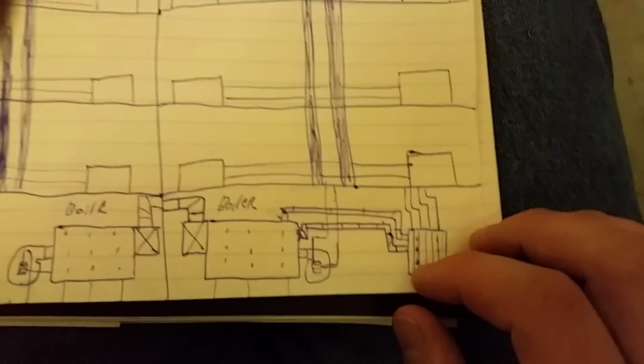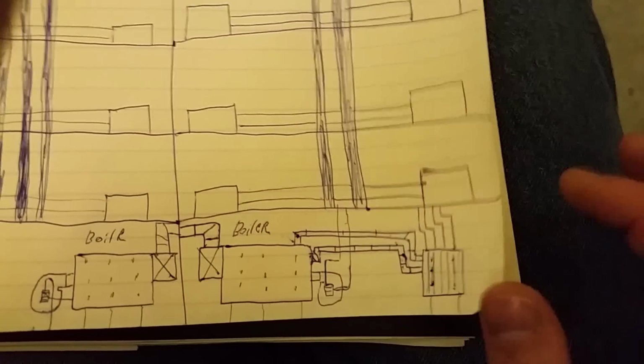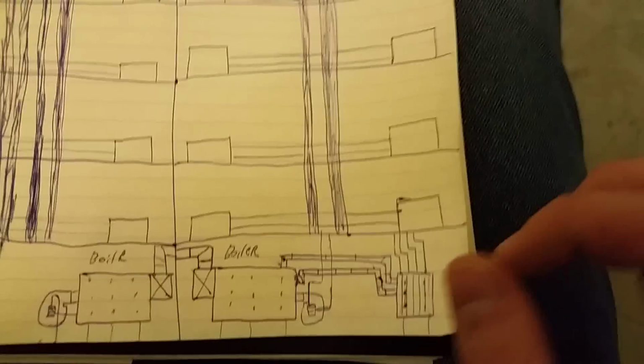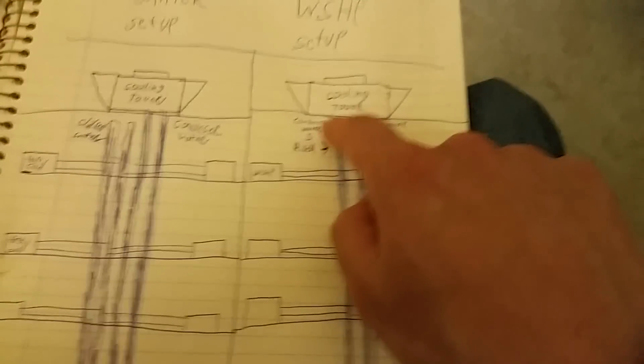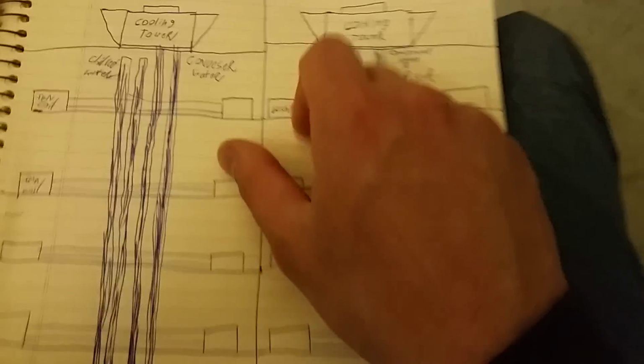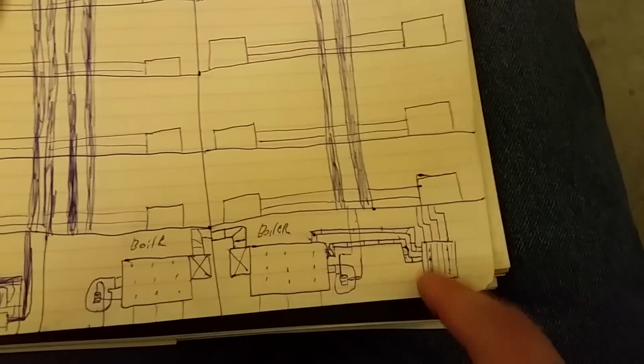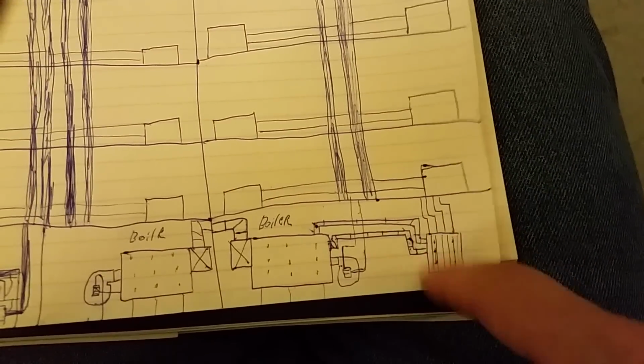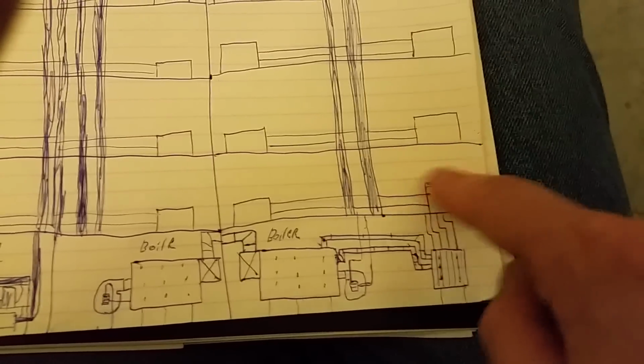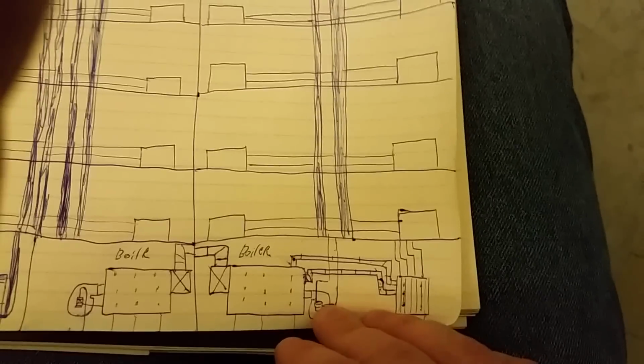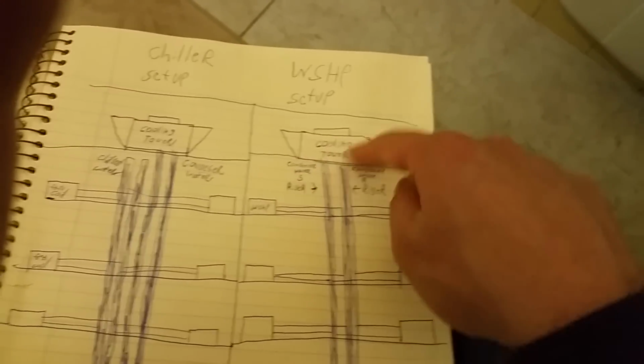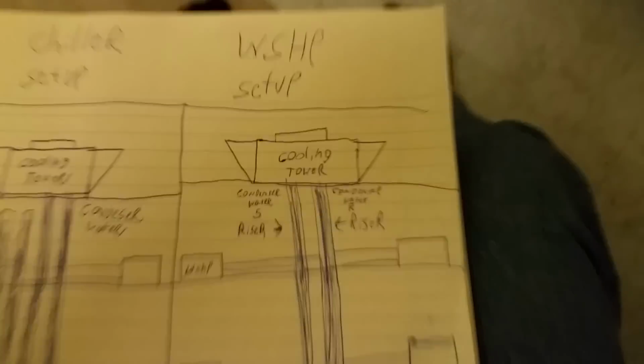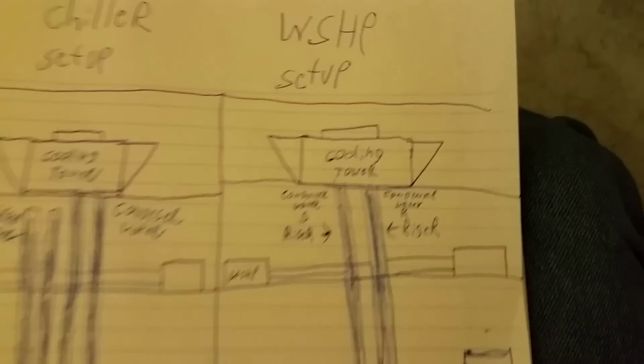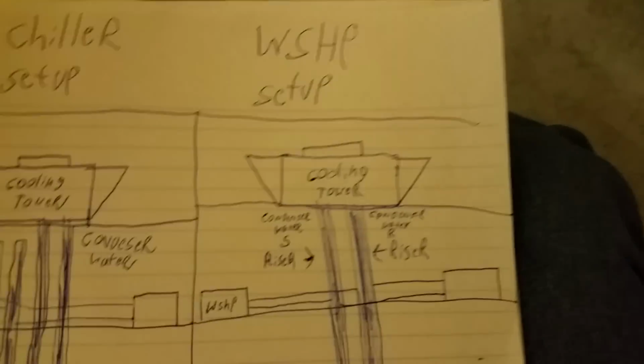You don't want to get a serious temperature change, so you crack the valve slowly and let a little hot water in. You want your loop to be in the 70s so these units can pull enough heat out of it. And then that just goes back to the water. All that cold water comes back to the boiler through the heat exchanger there and just gets recirculated, reheated. That's if your units are off the building boiler. Sometimes you will have an auxiliary heat, and this won't be necessary, but I'm pretty sure you would cut these off and drain the tower, just so it doesn't freeze and nothing cracks. So if I'm wrong about that, let me know. If I'm right about that, hey, cool.